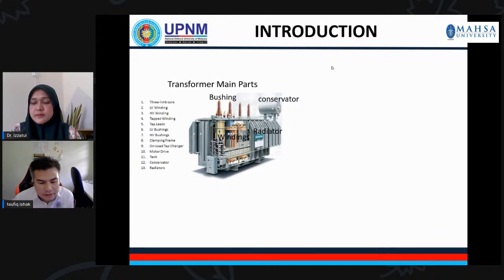Let's go deeper into the parts of the transformer. What are the main parts of the transformer? As you can see here, we have a bushing. The bushing is located at the top of the transformer, where it works as a gap distance between the transformer tank and the live wire from the transmission line.